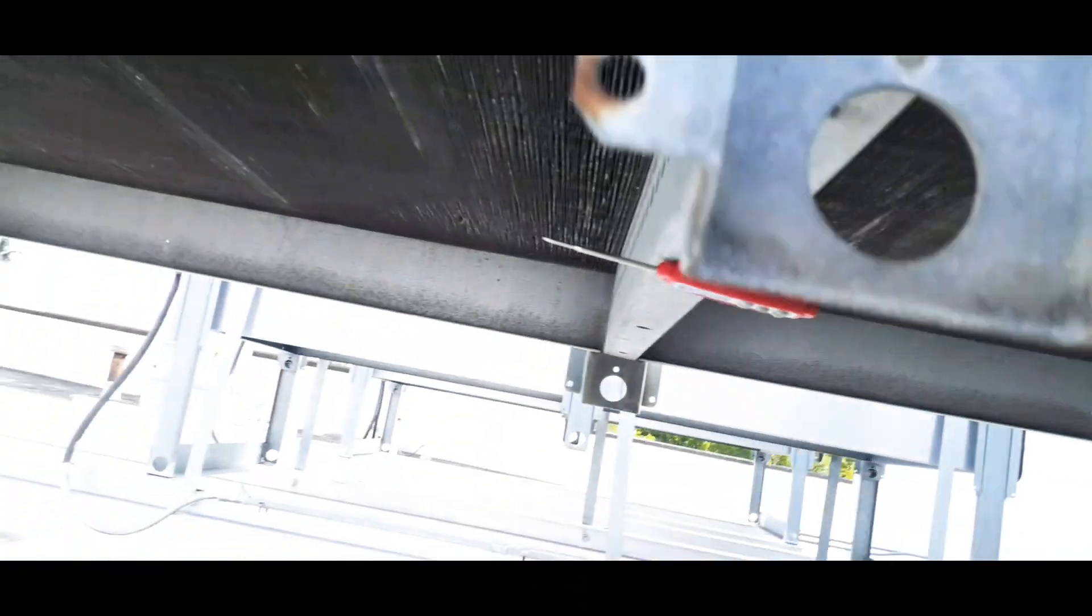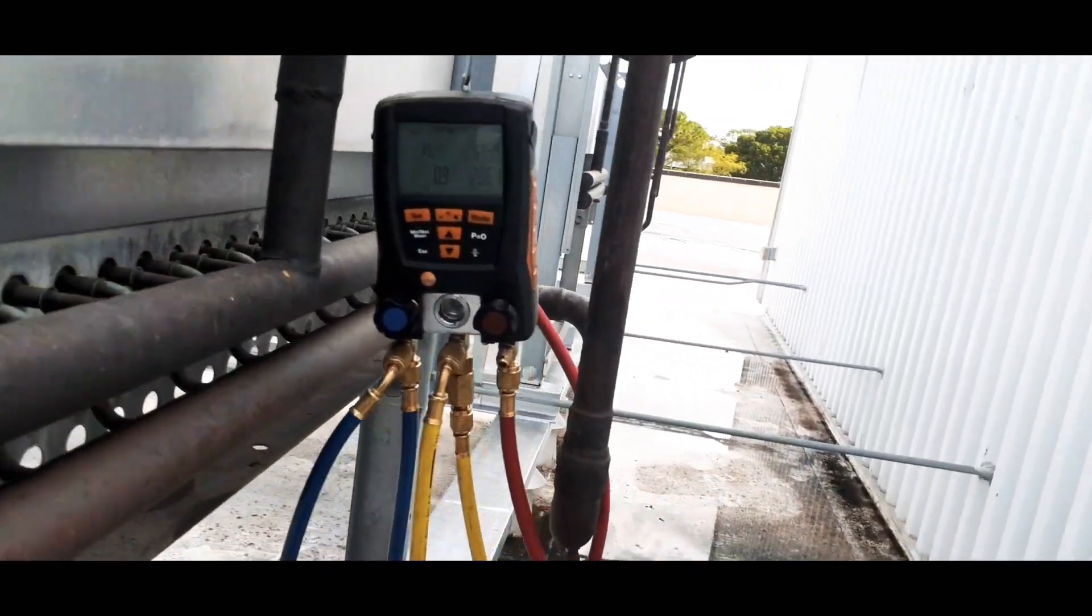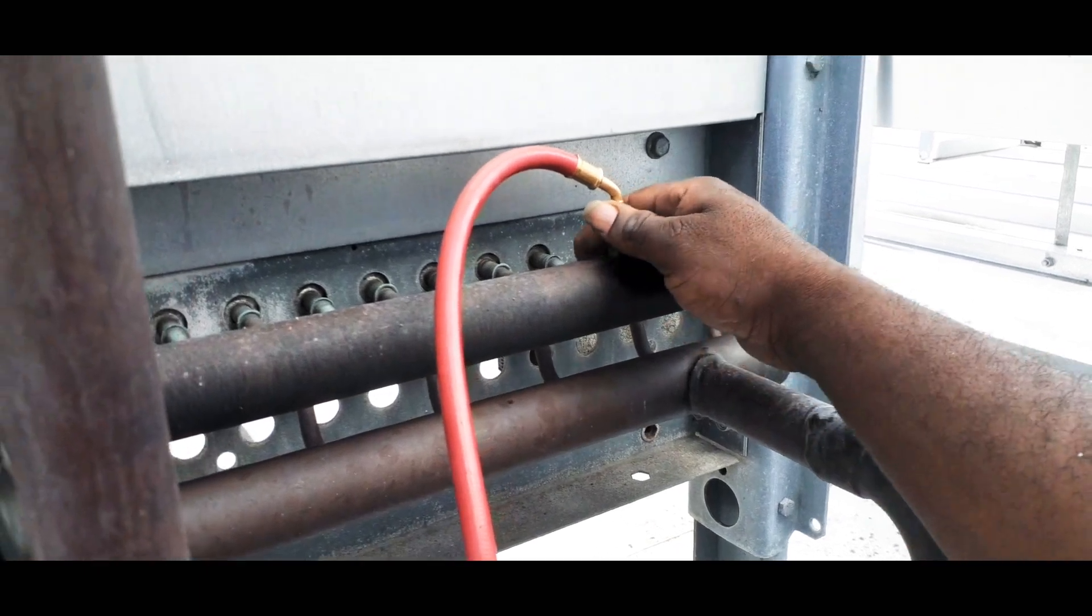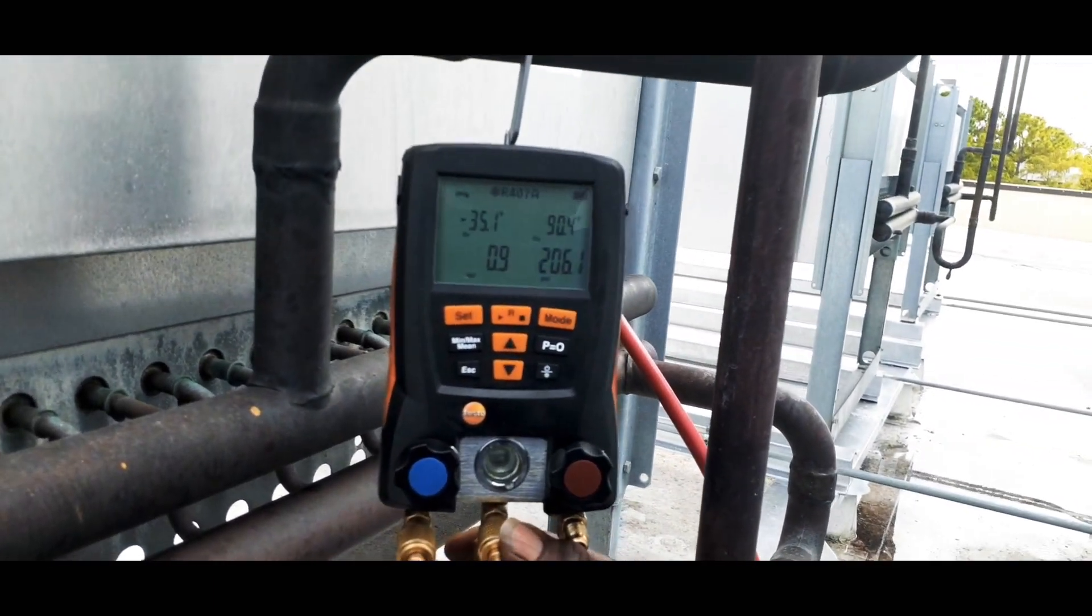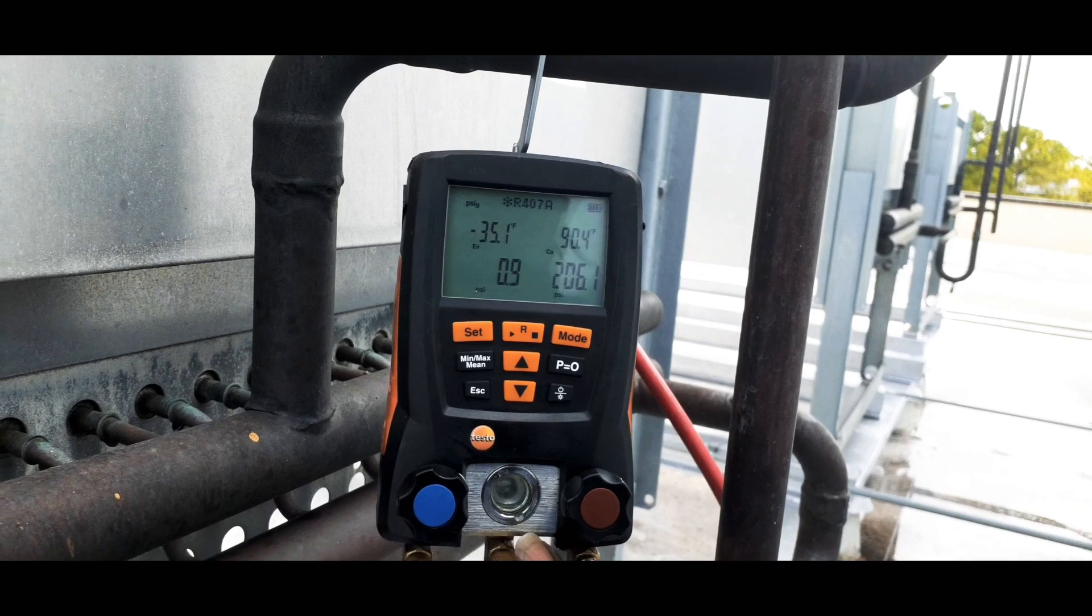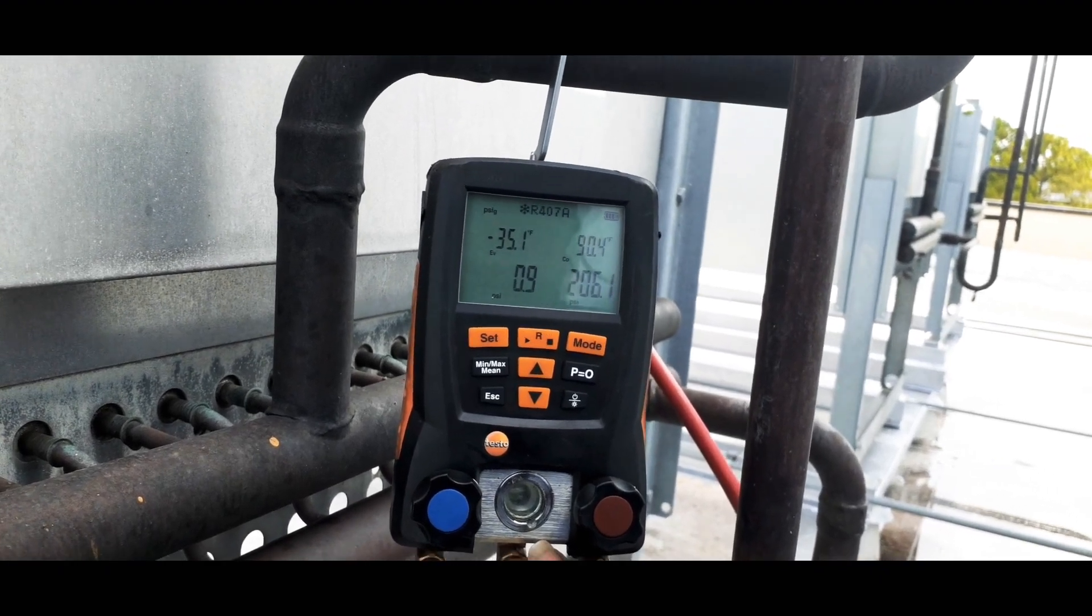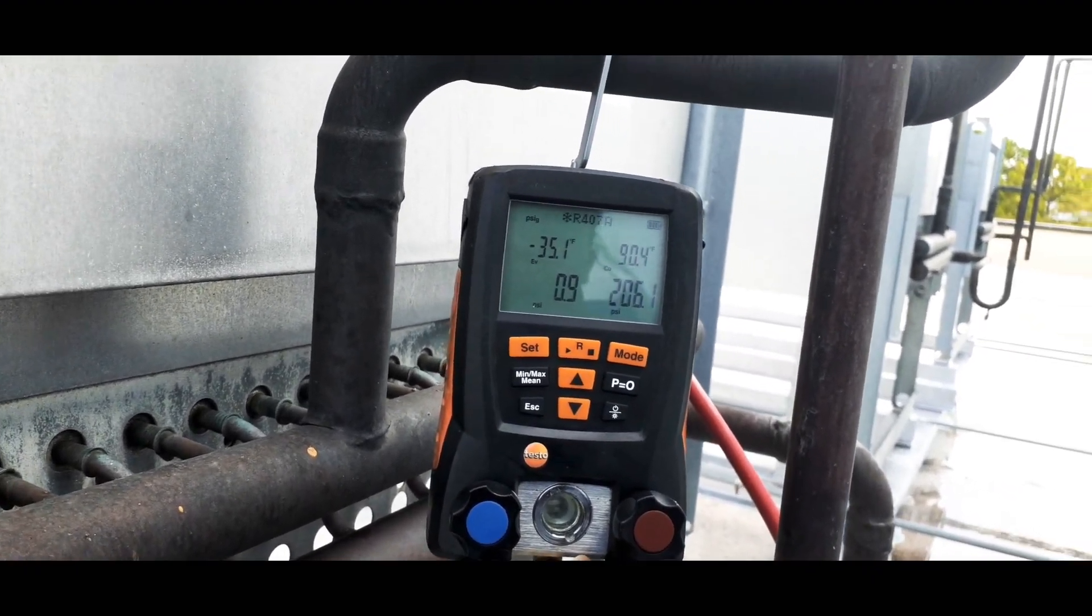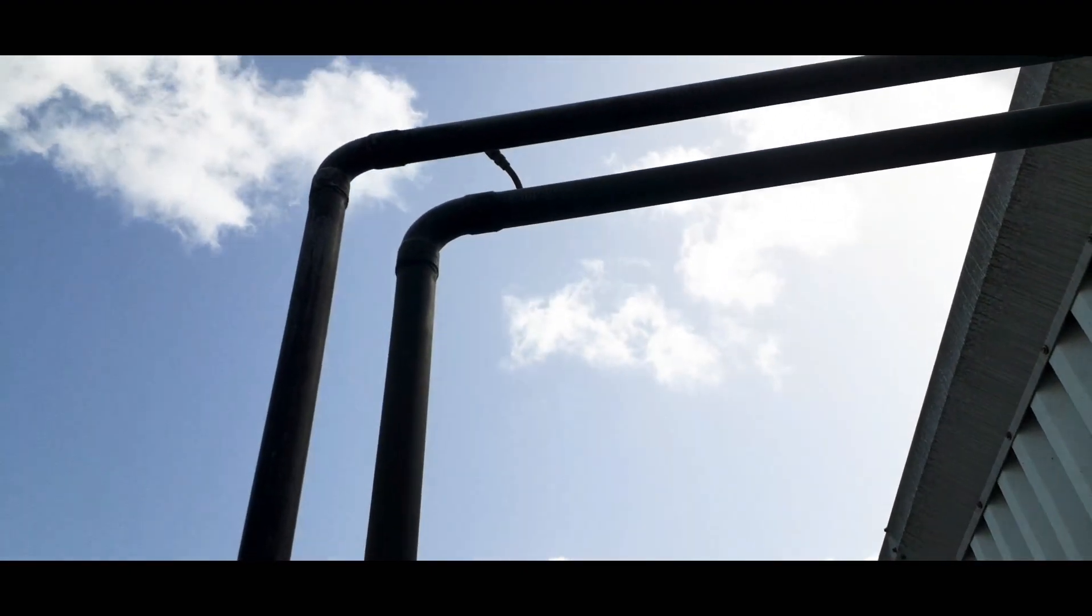I've got my gauges already hooked up right here on the high side. Basically we're at 206, so seems like there's some non-condensables in this rack. Normally you could probably recover some gas off the top right here off the high point.